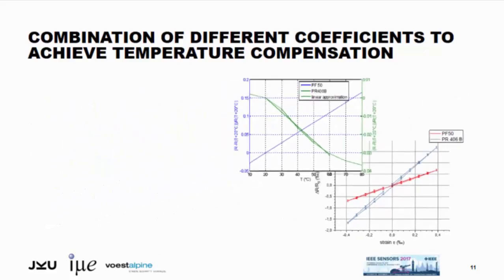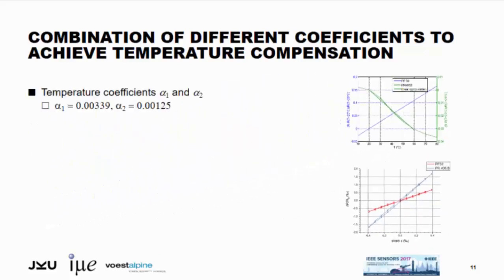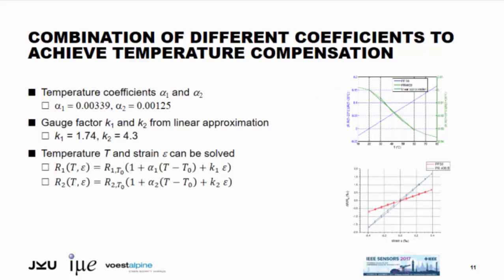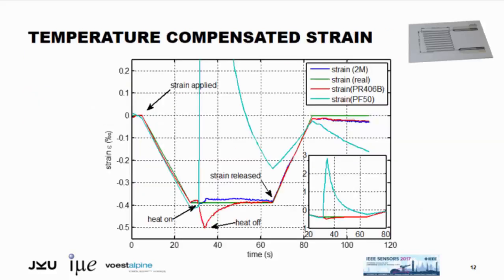So, what do we do with this now? We extract the two temperature coefficients, as I said before. We extract the two gauge factors, as also mentioned. And then we apply a set of linear equations which contain both the temperature and the strain. And now we measure temperature and strain on the same sample and employ the known values which we extracted from measurements before. And then we can calculate out of these equations because we just have to measure both resistances. Then we can calculate the temperature as well as the strain that was applied.